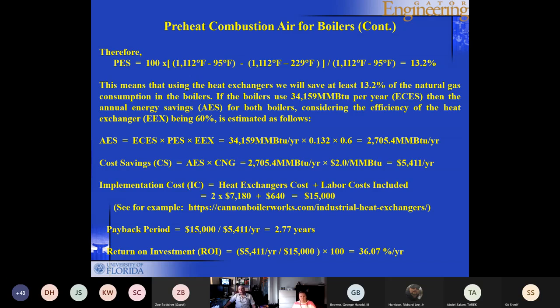If the boiler uses, let's say, 34,159 million BTUs per year, then the annual energy savings for two boilers, in this case we assumed we have two boilers, considering the efficiency of the heat exchanger being 60%, you can actually compute it, and you end up with 2,705 million BTUs per year as the savings. When you multiply by $2 per million BTUs for natural gas, you get $5,411 per year.